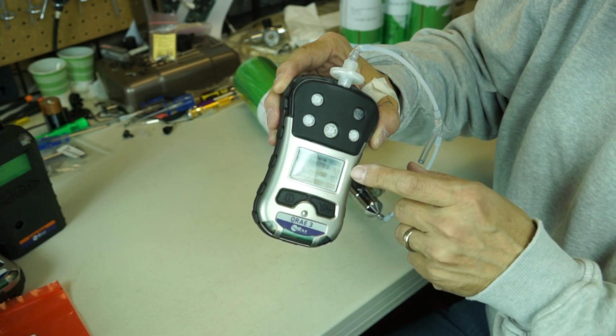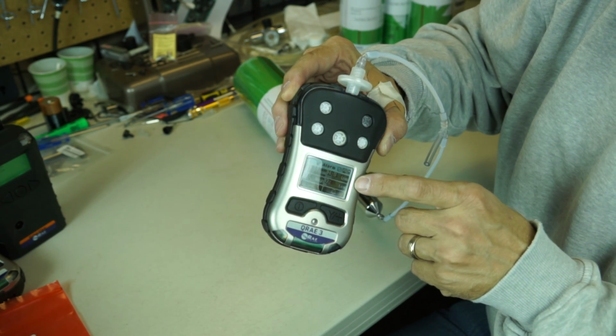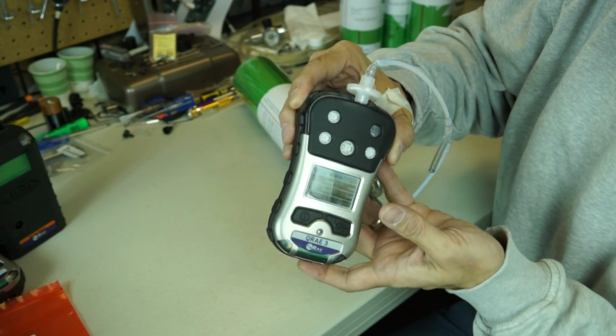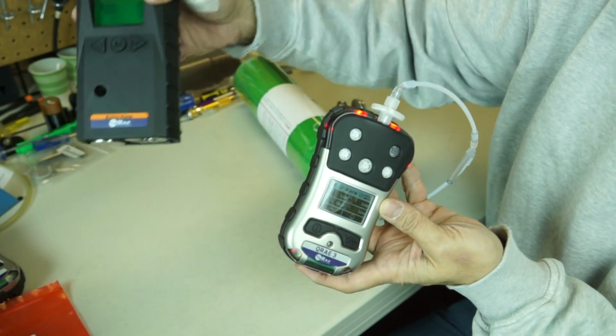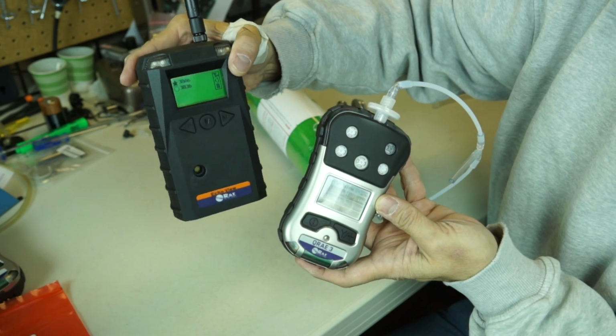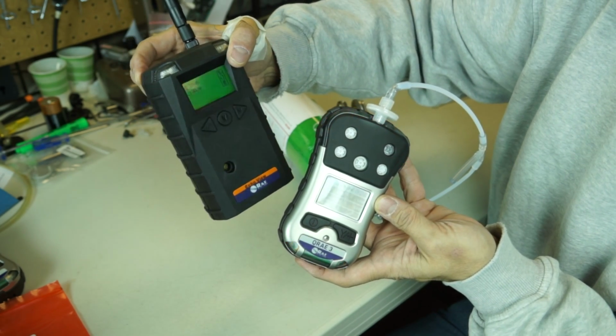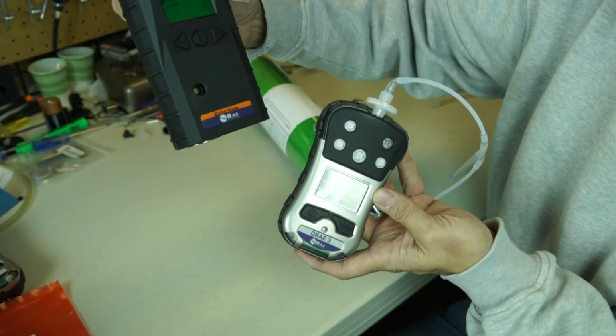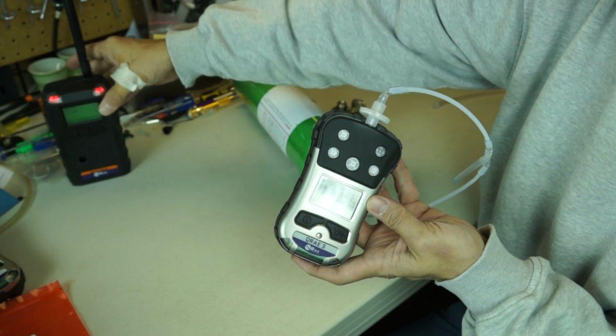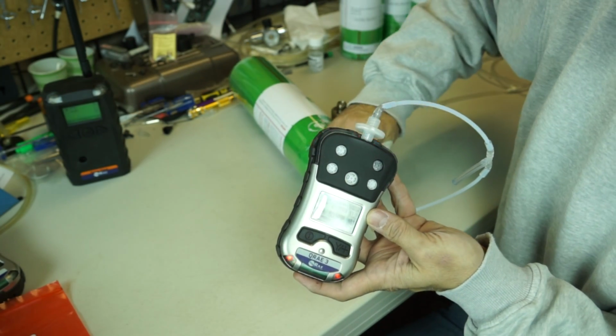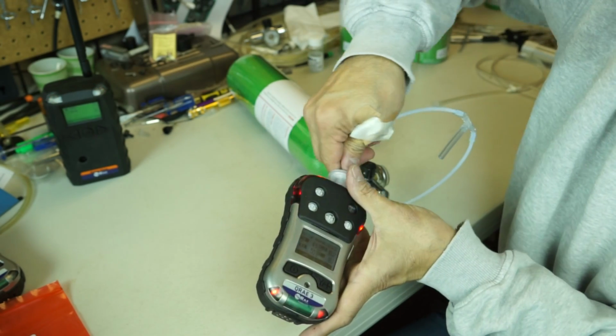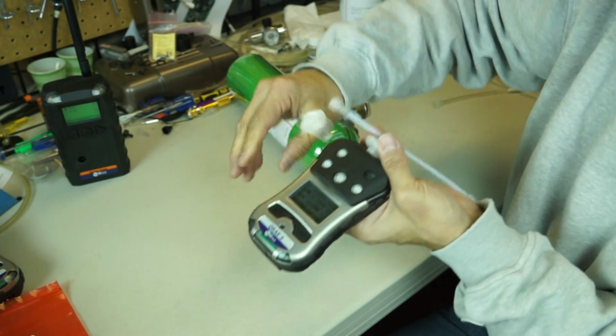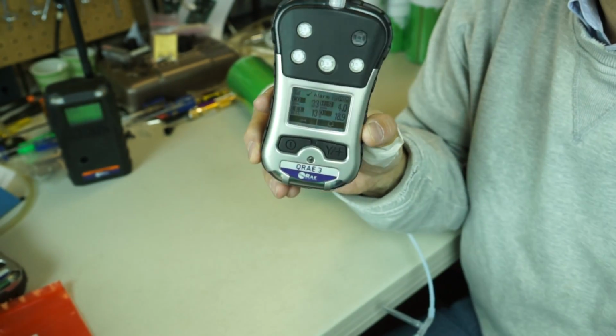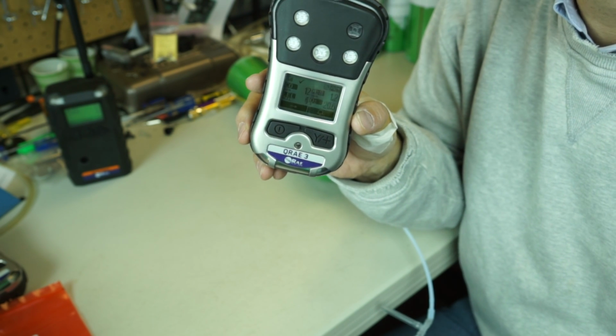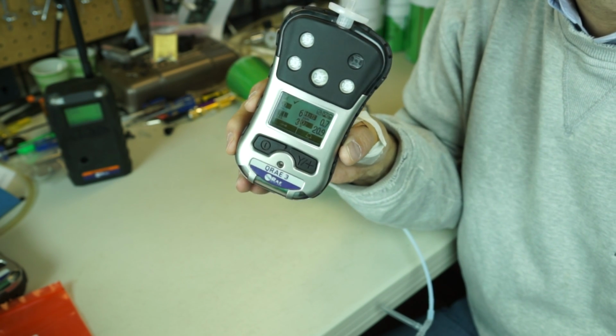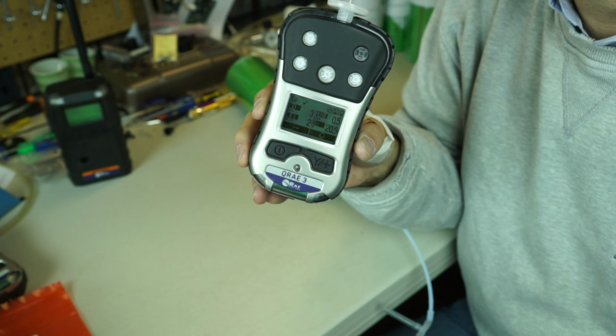And I can see all my sensors are in alarm. H2S, LEL, O2, oxygen. I can also grab my echo view, and the echo view is going into alarm because it's telling me one of my meters is getting gassed. And that's cool. So that's what's going on in the background here. It's a secondary thing. Shut my gas off. Disconnect. And the instrument shall slowly come out of alarm because we're not giving it gas anymore. And we go to work.